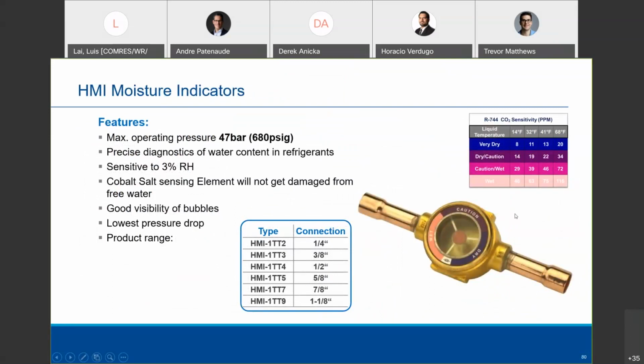One thing about CO2, it uses POE oil. And it's important to note that in POE oil, you don't want to get any more than 75 parts per million of moisture in that oil, or you can start to get acid formation. So it's super important to understand that your refrigerant is kept dry at all times. And this cobalt salt element that's used in this sight glass, the one in North America as well as the one in Europe, has been around for 30 years and is still the most sensitive element in the industry. And we have a chart that can tell you what the temperature of the liquid, the color, what the parts per million of moisture is in that system.